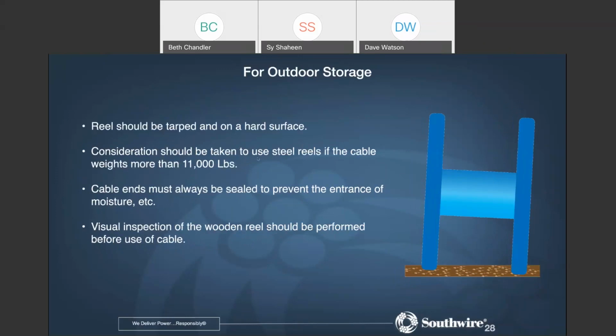Again, you should use steel reels if it's more than 11,000 pounds. Make sure you seal the ends and visually inspect the wooden reel. And if you do use a wooden reel, make sure you look at it before you take it out, and make sure that both the reel and the cable are in good condition. Because frankly, the cable might be in good condition, but if the reel is bad, well, you can't really unreel it.